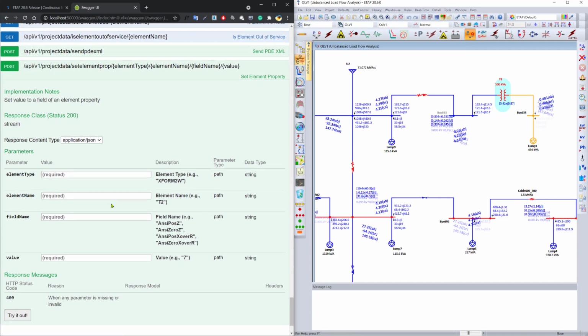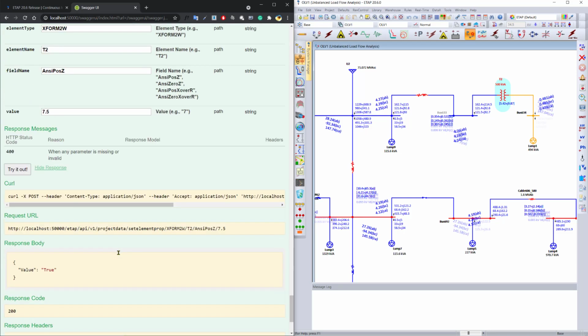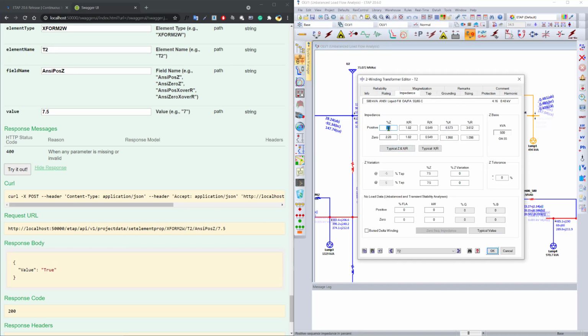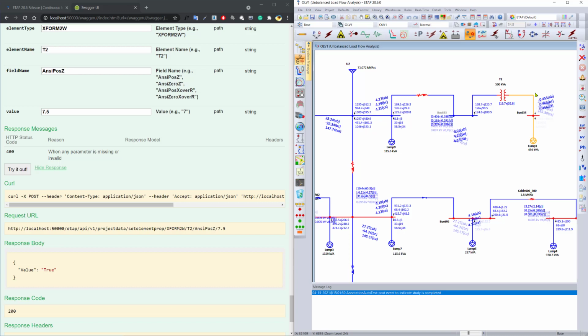You can also use the same tool to set the value of the property for this element. We set the value for the ANSI positive sequence impedance, and the value we would like to set to is 7.5. And we can go ahead and apply it, and then open up the program to make sure that it actually has been applied. And once that has been applied, you can rerun the calculation, and you will see different results.